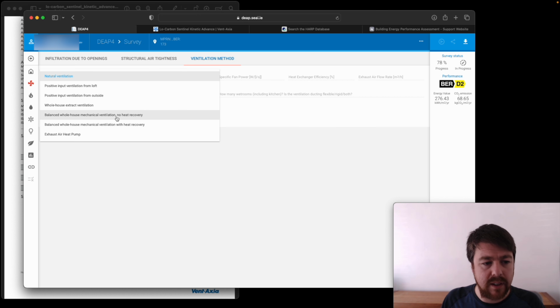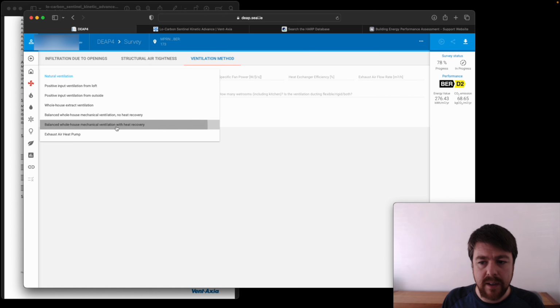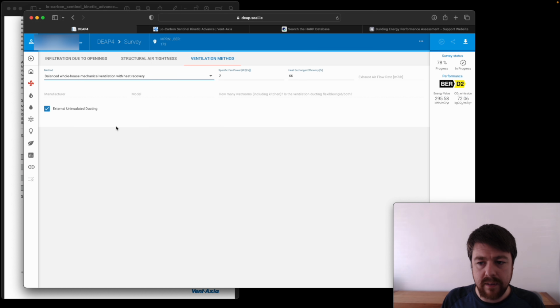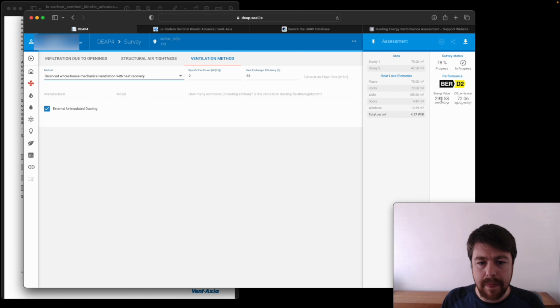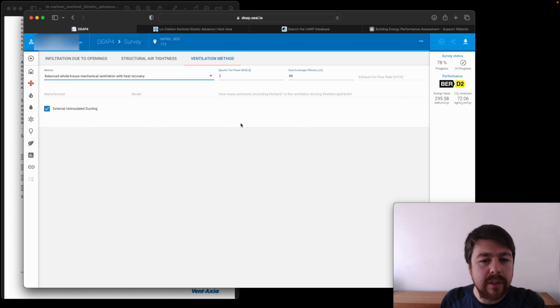So 276, but if I put in balanced heat recovery ventilation, it increases energy consumption. What we have to fill in is our specific fan power in watts per litre per second, and our heat exchanger efficiency. These are extremely conservative, energy inefficient values. We can do far better than this.